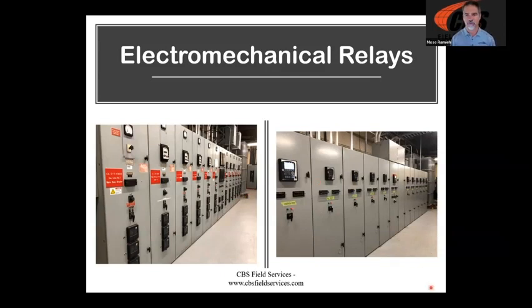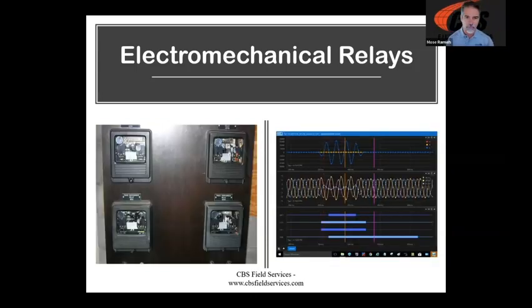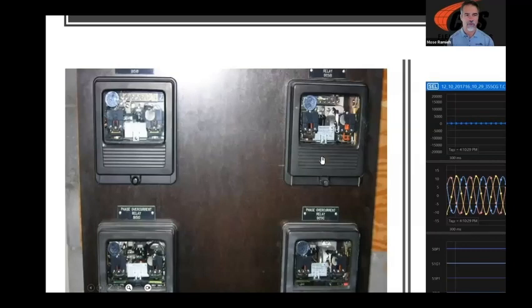But what are some of the advantages of that, right? Why do I want to go through all the time and the trouble and the money to upgrade my relays? Well, a couple of different reasons, really. And one I want to point out, of course, is one of my pet peeves. You're walking around and there's a target on the relay. Well, in the old days, that was all we do is, yep, we had a trip, right? That's what that little orange window is telling me. I had a trip. Doesn't tell me anything about the trip, right?